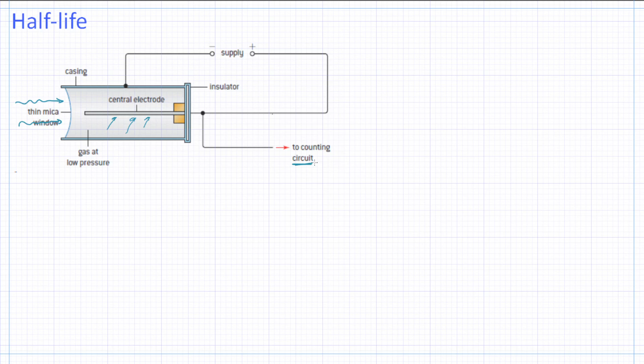When we want to measure the decay or the radiation for beta or gamma decays, we need a device called a Geiger counter. Strictly, it should also be called a Geiger-Müller counter. So how does it work? We've got a tube here filled with a low pressure gas, and our radiation is going to enter through this thin window here. When radiation goes inside of this chamber, it will react with the gas, and it will ionize the gas. When this gas is ionized, here there will be some supplied power. So when this is ionized, it will feel attracted to the central electrode. And then there will be some difference in electric potential, and then it can be measured. There will be a pulse traveling here, and then we can detect it.